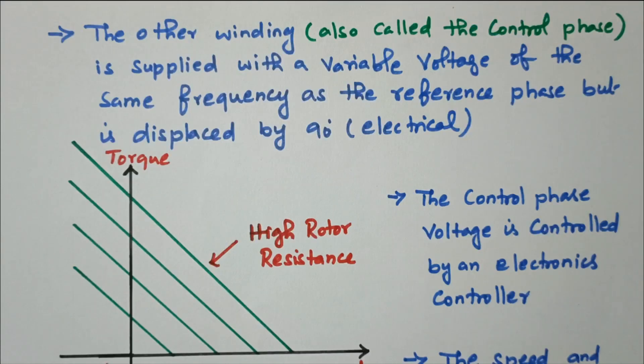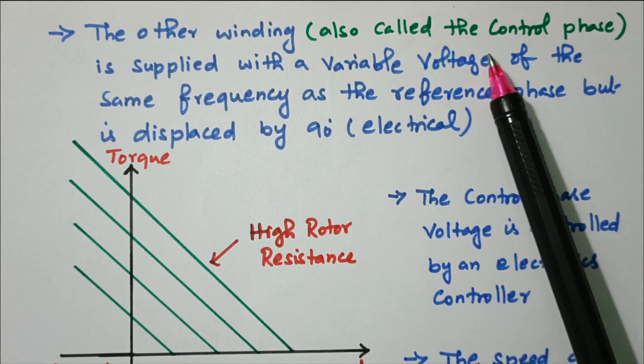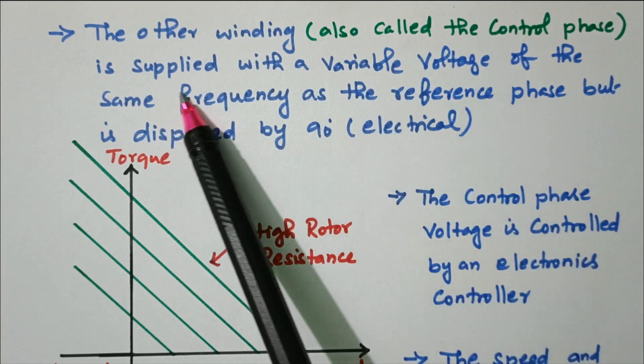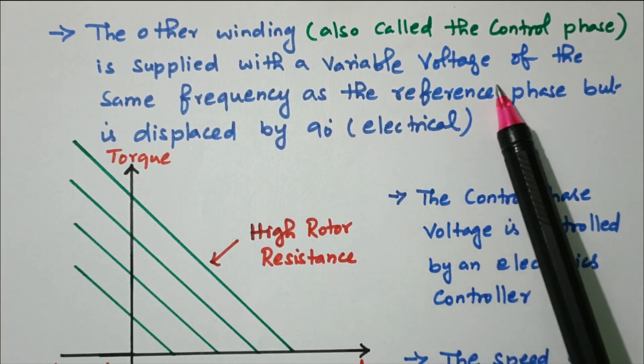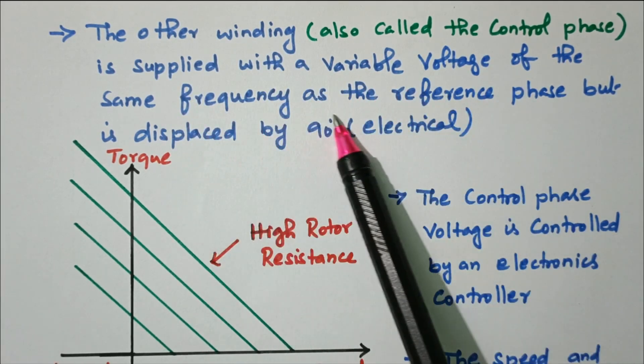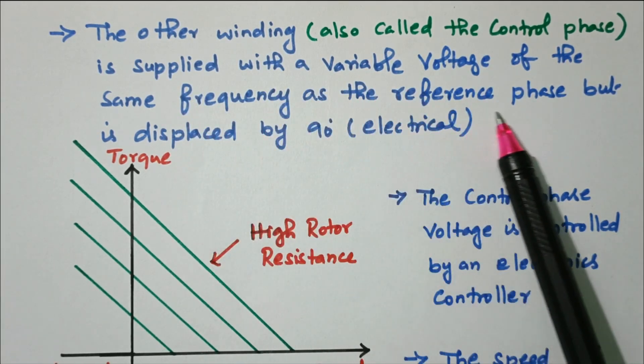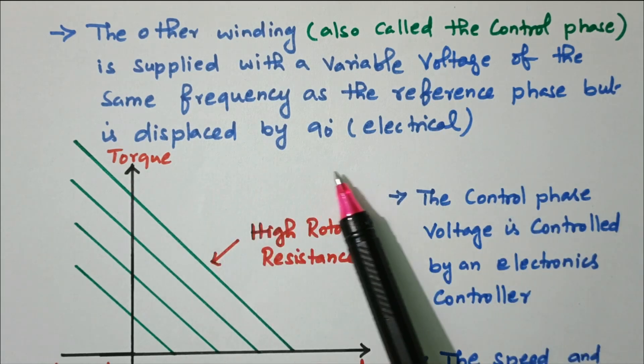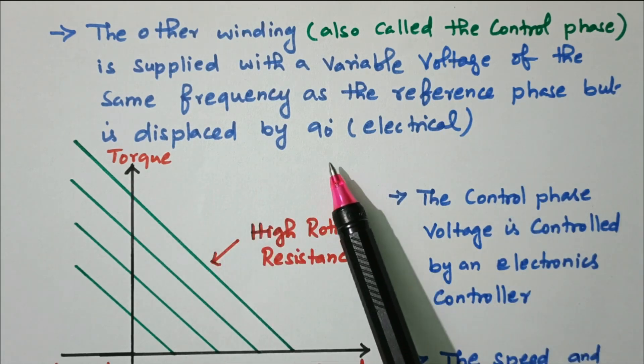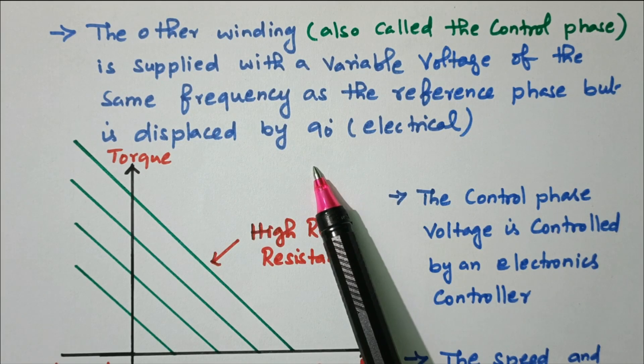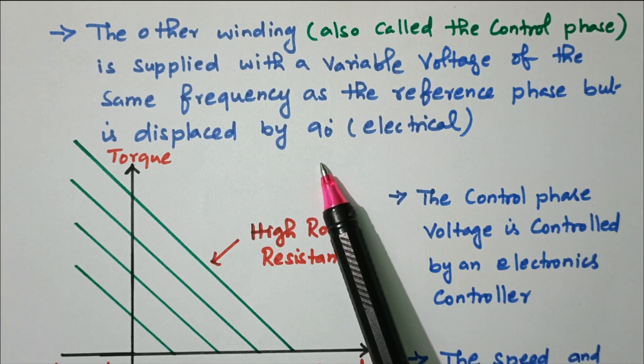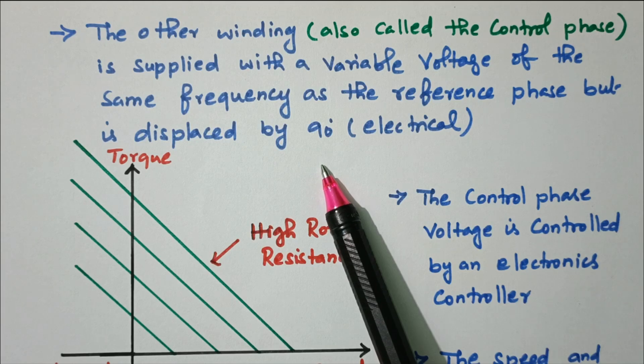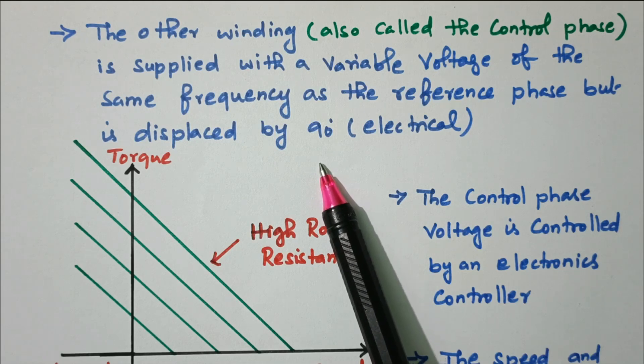The main winding, also called the reference or fixed winding, is supplied from a constant voltage source Vm at angle zero degrees. The other winding, also called the control phase, is supplied with a variable voltage of the same frequency as the reference phase but displaced by 90 degrees electrical. This 90-degree phase difference between control phase and fixed phase gives us position or speed control for any small change in voltage or current.